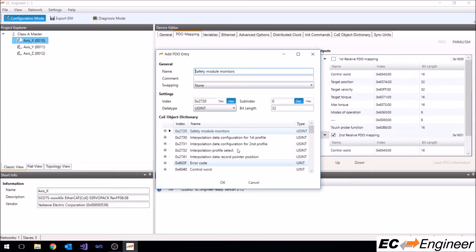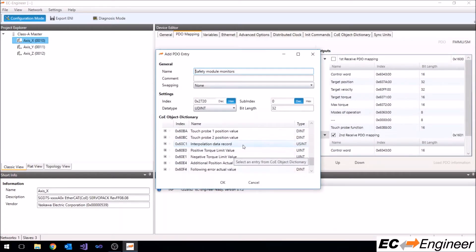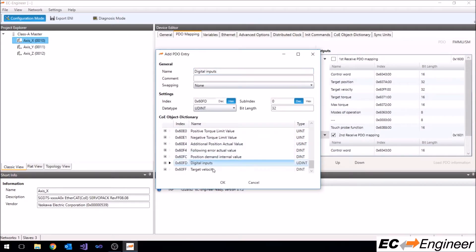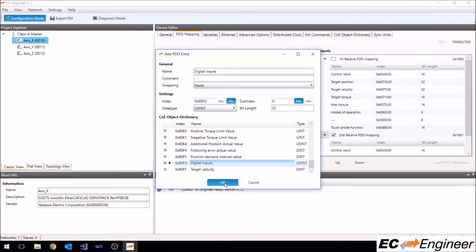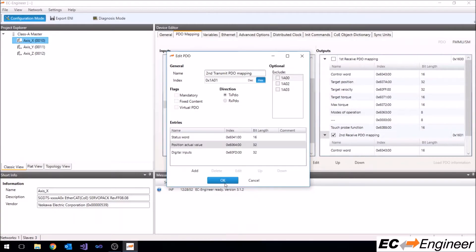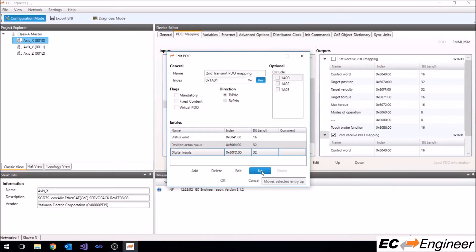Click the add button and select the entry you wish to add. Here we will add the digital inputs from object dictionary entry hex value 60FD. Now you can see the new entry is part of the second PDO.